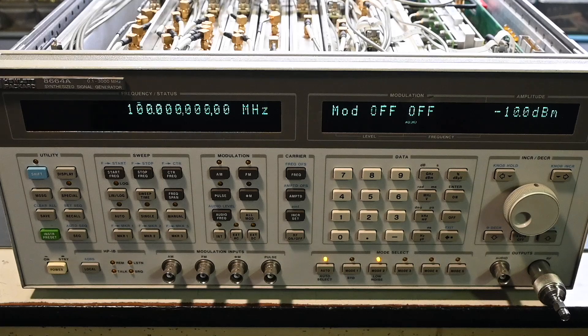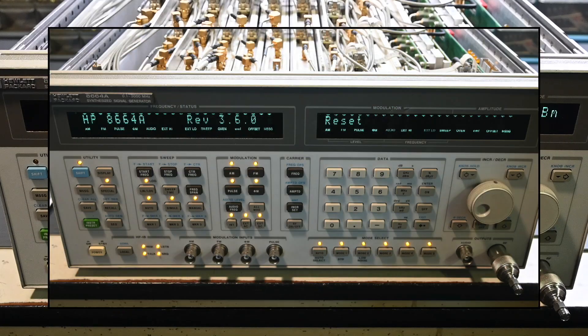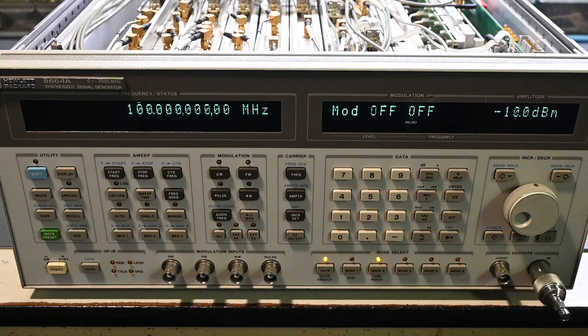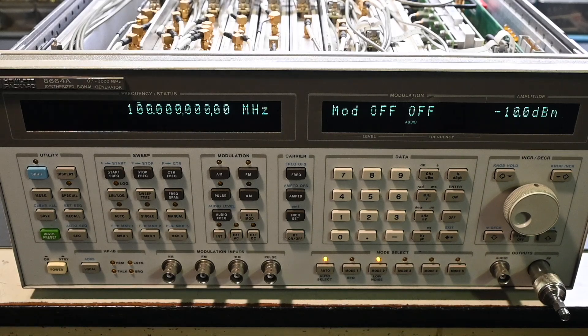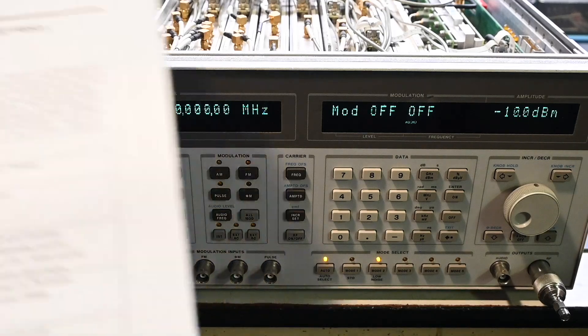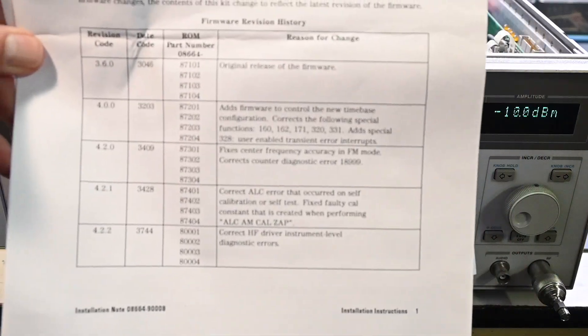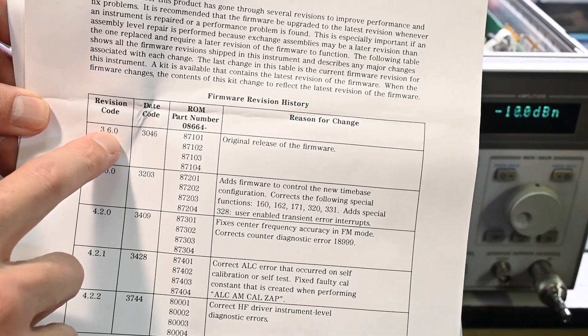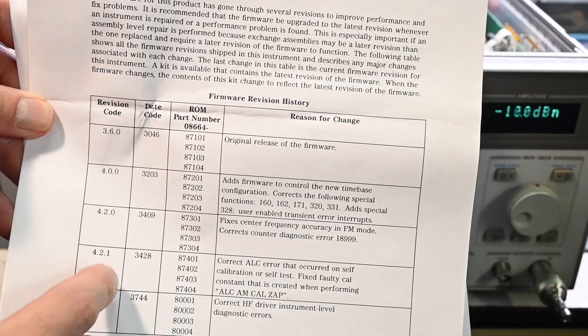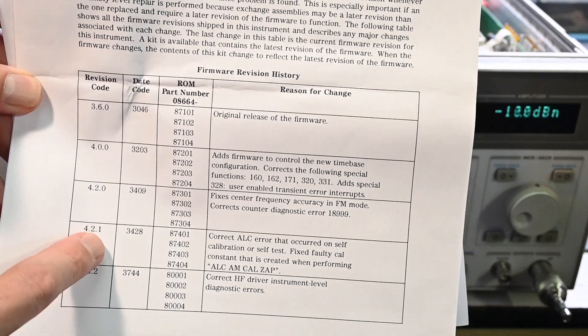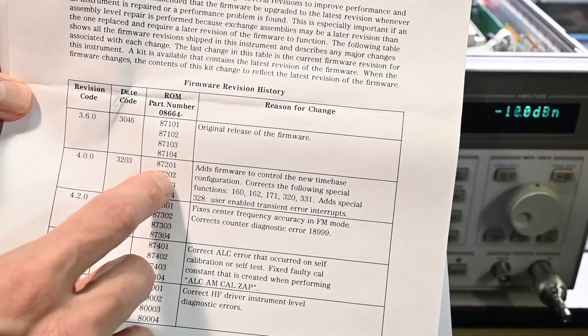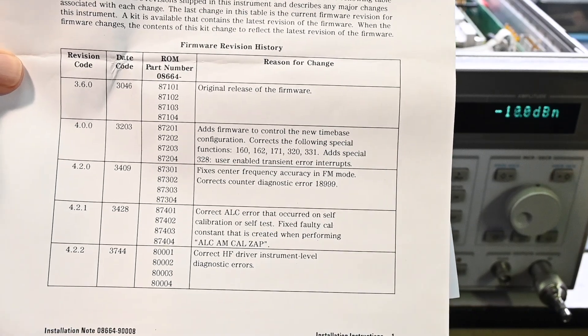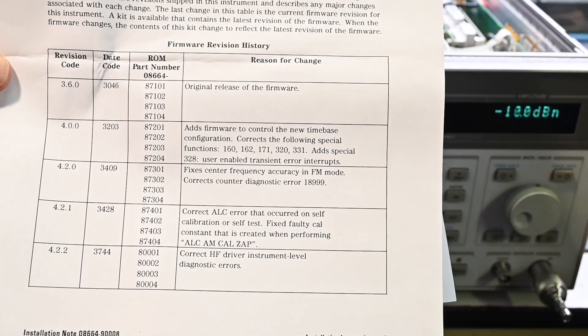Okay, so this signal generator has the original firmware version of 360, and that's the initial release, and I wanted to update the firmware. The latest version that I was able to find is version 4.2.1. So let me grab this chart right here. So again on this chart, we're up here in 360, you can see original release of the firmware, and down here 4.2.1 is the version that I was able to find. As it goes along on this chart, you can see some changes that were made right here, so these are rather important things that were corrected and fixed.